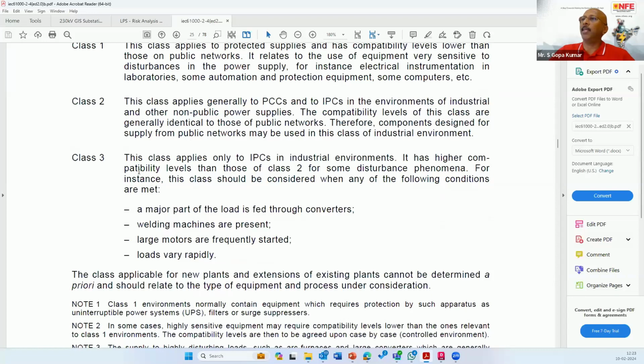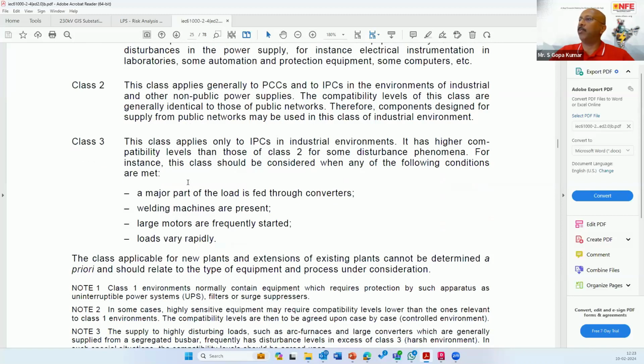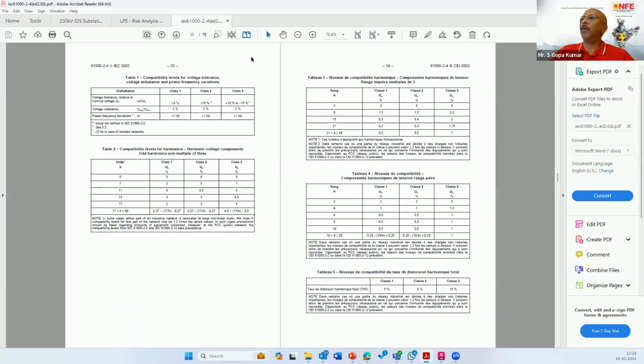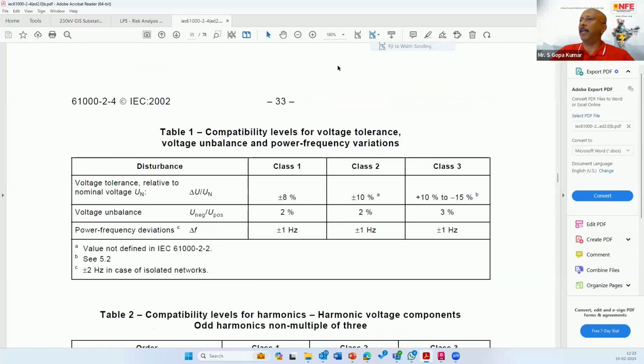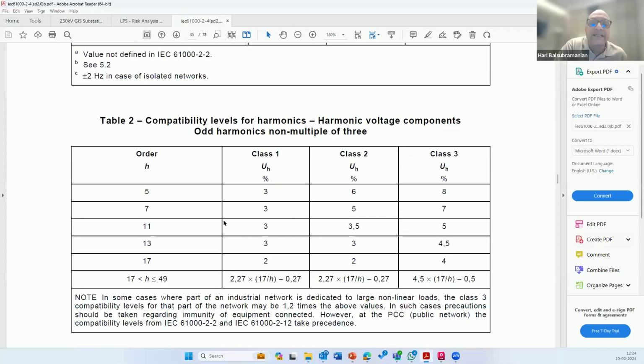Class 3 applies only to IPCs in the industrial environment. It has higher compatibility levels than those of class 2 for some disturbance phenomena. For instance, this class should be considered when any of the following conditions are met: a major part of the load is fed through converters, welding machines, large motors, or frequently and very rapidly started loads. So basically, the definitions are very clearly given, and Table 2 explains the limits. Am I correct to read it this way? Correct. Okay. Thank you very much.